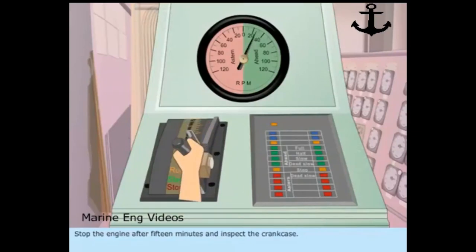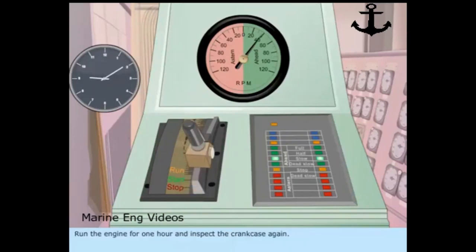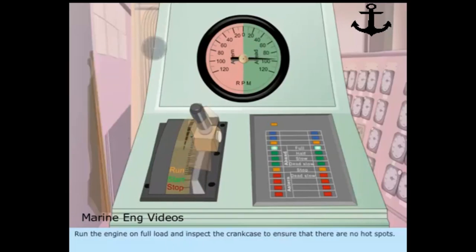Stop the engine after 15 minutes and inspect the crankcase. Run the engine for one hour and inspect the crankcase again. Run the engine on full load and inspect the crankcase to ensure that there are no hot spots.